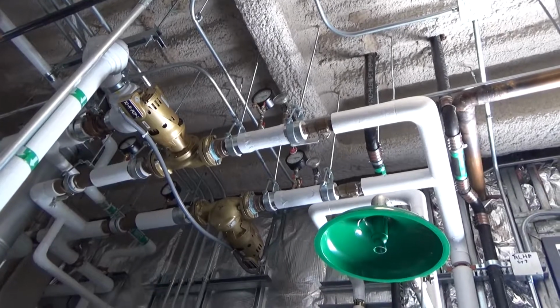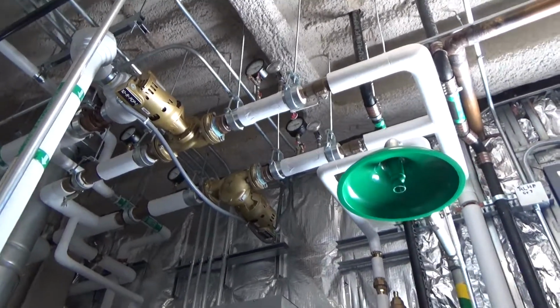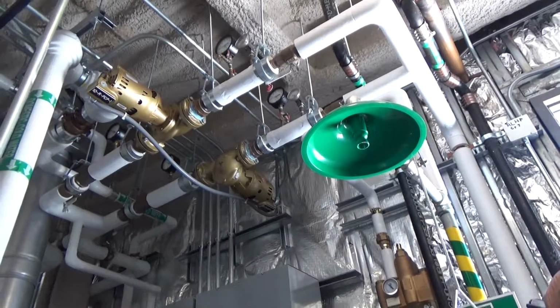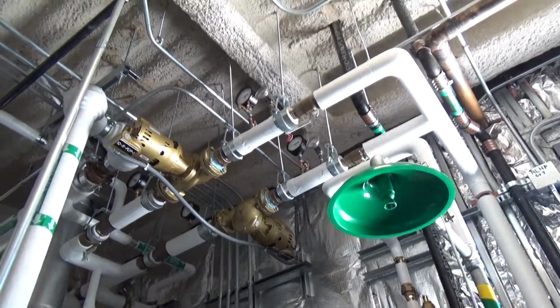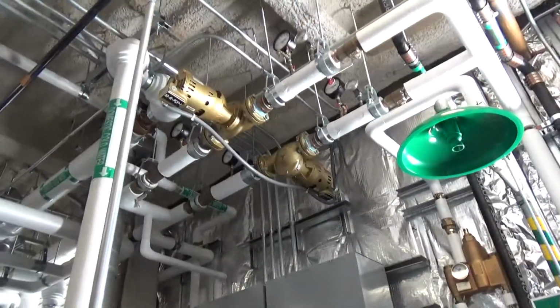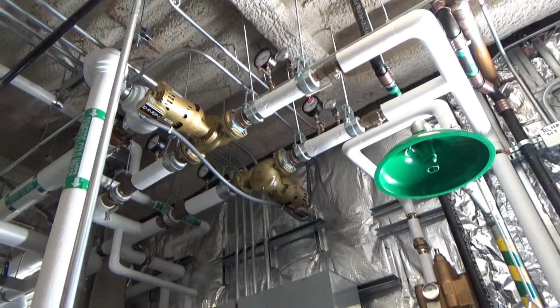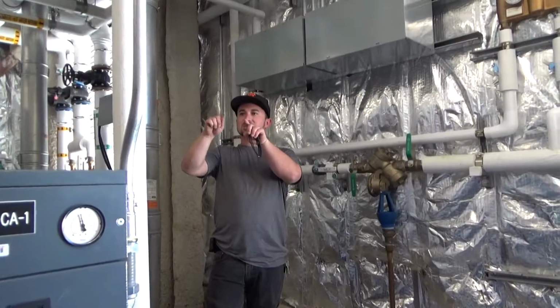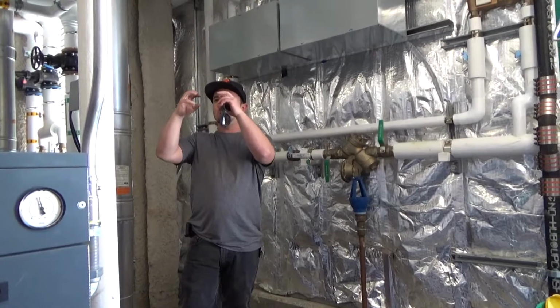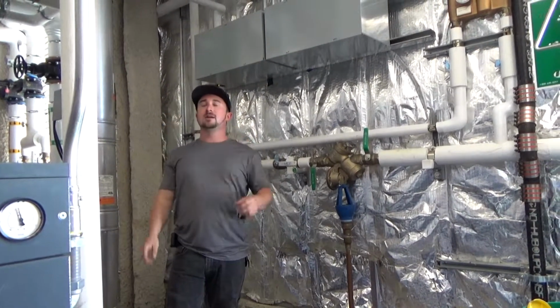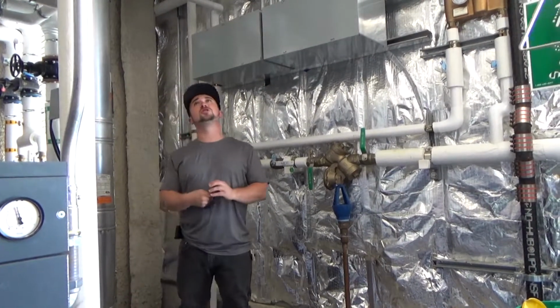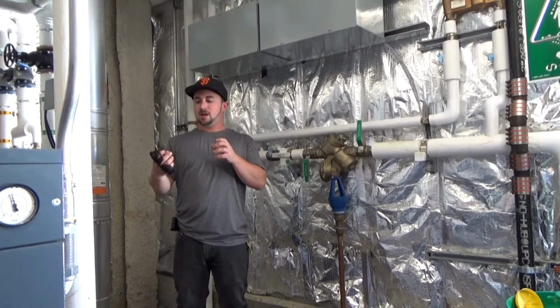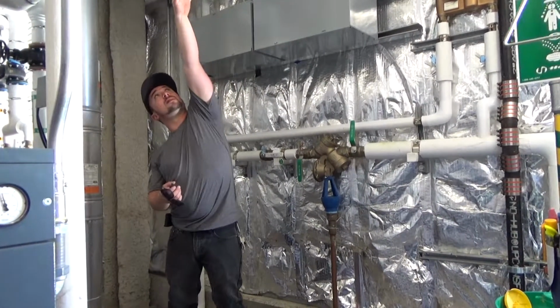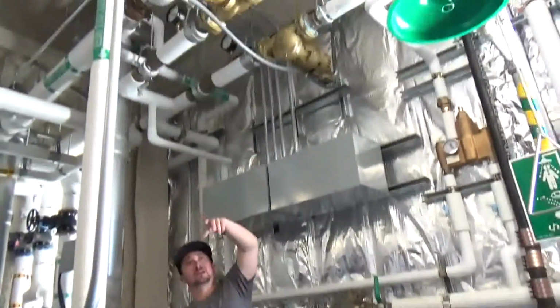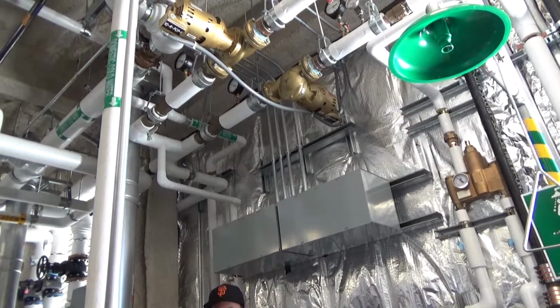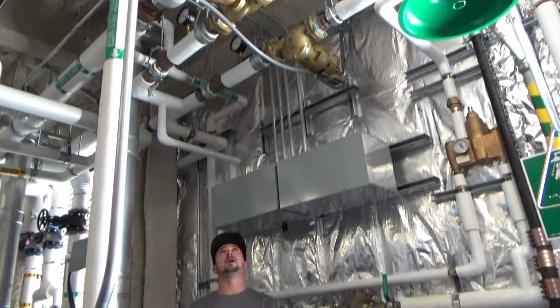Is there a coupling on these, or is it direct? Yes, there is a coupling. It's called a Woods coupling. It's like a little black spider-looking one. It's two little hubs with a little insert in the center. When you pull that apart, on the top, in between the motor and the volute, there's a little metal plate that comes out, and that's where you can see your coupling.